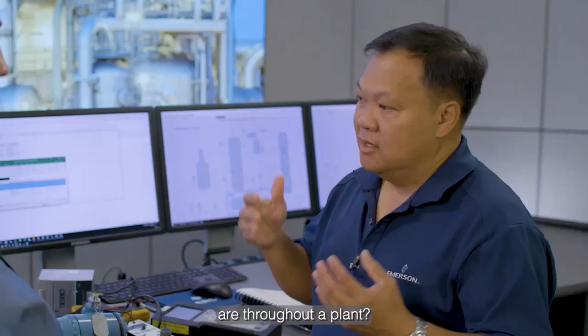And that's just one device. How many devices are throughout a plant? If you start up a single section of a plant, it could be 40 to 100 devices - that would take a month or so. Then the whole entire plant could range up into the thousands of devices. You just calculate that - it could take a year or so to start up a plant.